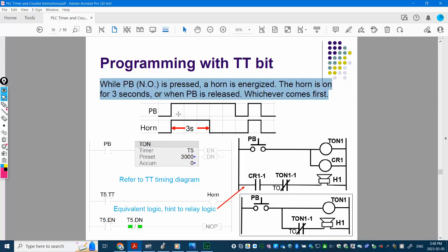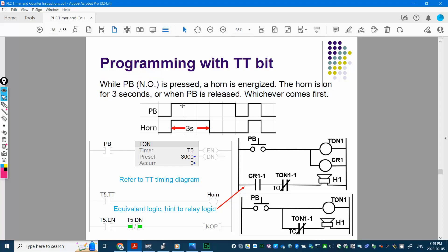Looking at the timing diagram, when PB is pressed the horn will be energized for three seconds. In the first situation, you can see the PB is pressed longer than three seconds — maybe five seconds — but the horn is only energized for three seconds. For the second case, the PB is pressed for only one second, and then the horn is only energized for one second. So whichever comes first: the longest is three seconds, but it could be shorter.